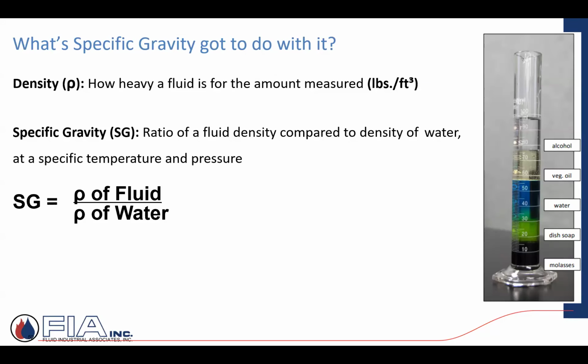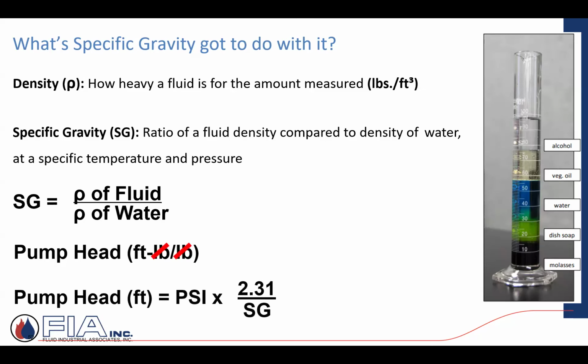This is just getting into specific gravity and how it can influence the amount measured in pounds per foot. We don't need to spend a lot of time other than knowing that there are different properties. Water is what we're typically going to be dealing with, but you could get into some type of process, maybe an oil or a gas, in some type of mill or processing, and it will influence the pump curve, the feet of head.